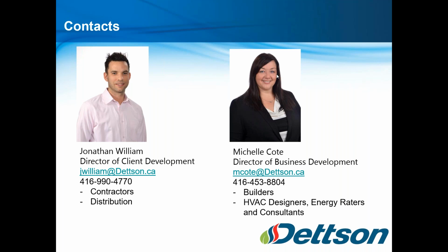Now, I will tell you that we have had some experience in renos and some other work we've done, that if you do a substantial reno, not a gut rehab, and you add some insulation and air tightness, and yet you're not tearing the inside out, and you're not redoing the ductwork, and you're not doing the mechanical, and it is an air delivery system, we have found that because you are lowering the loads, you can't shrink the ductwork magically, but you may want to consider sealing the ductwork. The reason for that is to at least start to get the air where it needs to go and keep the pressures up in the system. There are lots of ways you can go back in and retroactively seal the duct system. I'm not going to speak to them because there are lots of proprietary companies that do that, but it does seem to have some benefit on the retrofit side in energy efficient renovations.